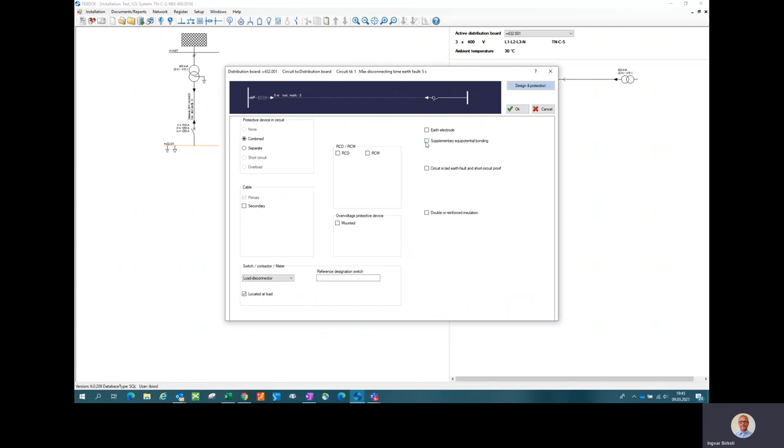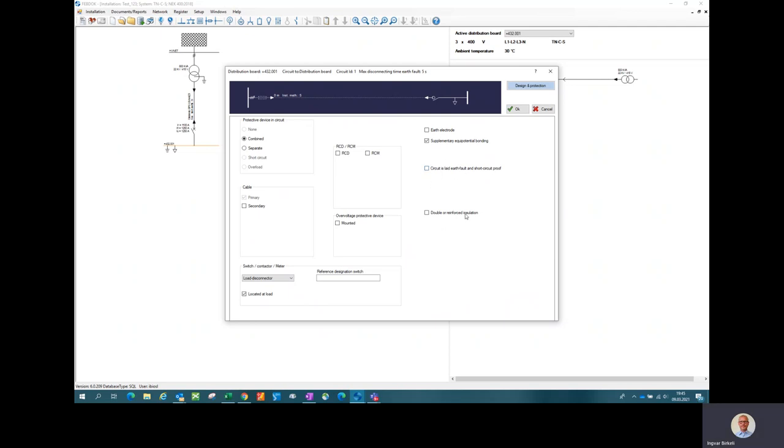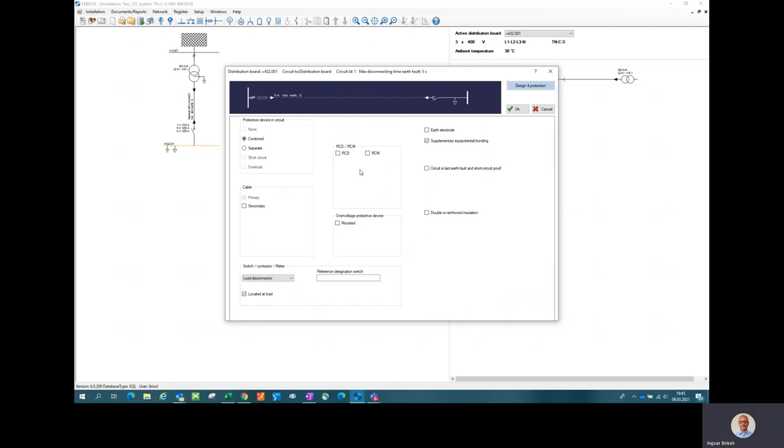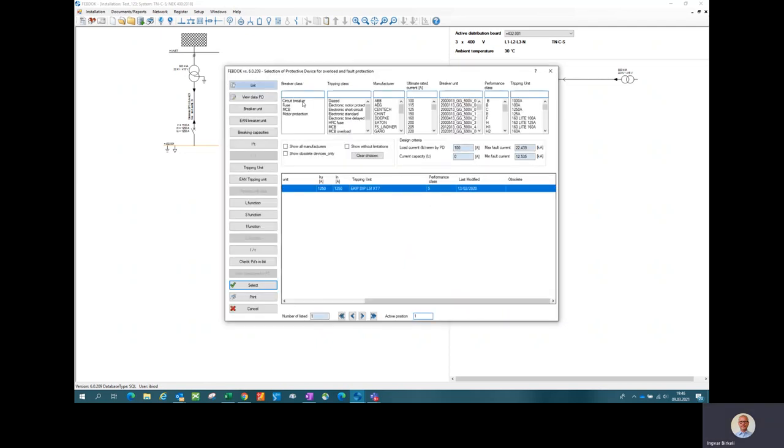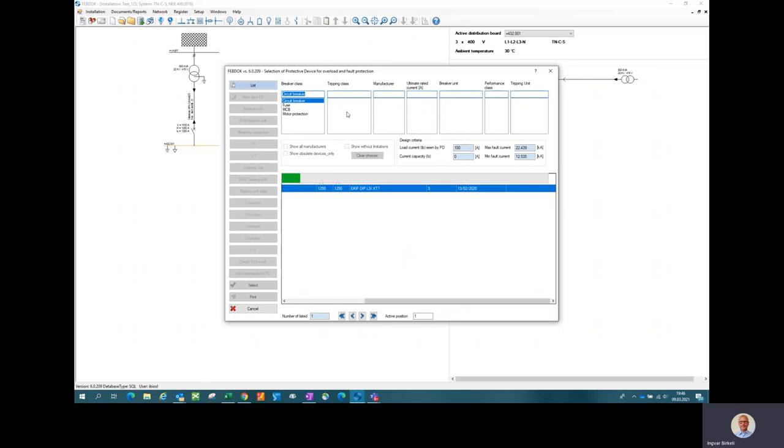Of course if the circuit has reinforced insulation or the cable is laid protected, you can choose that as well here. And you can choose if you have some earth leakage protection as well. I will not do any of those on this main circuit. Combined protection device would be good. And I come here and look for a suitable circuit breaker.